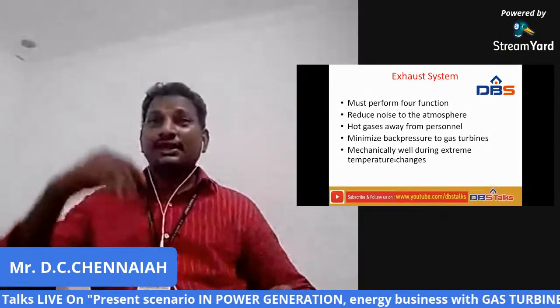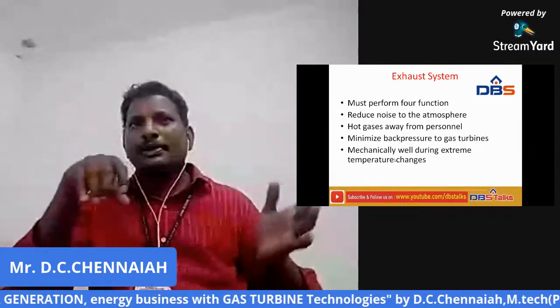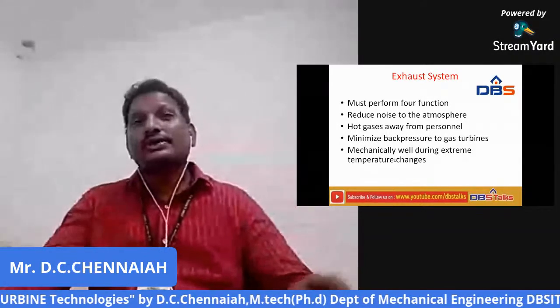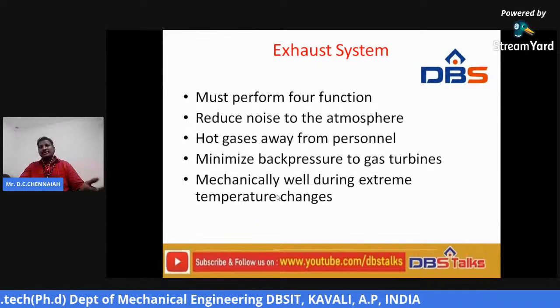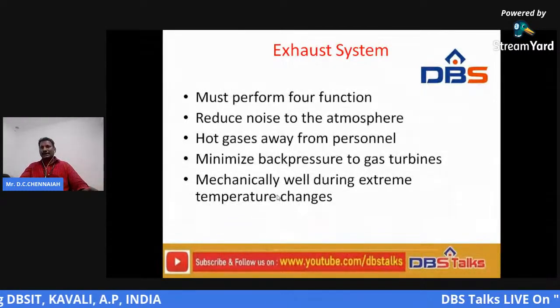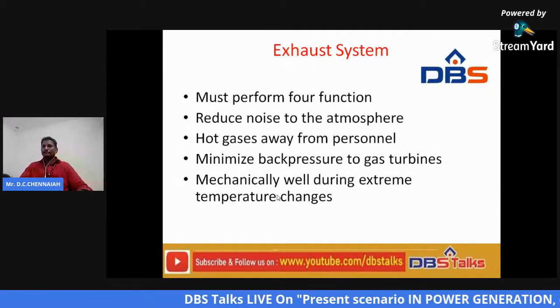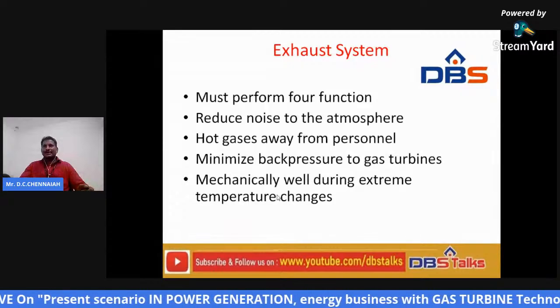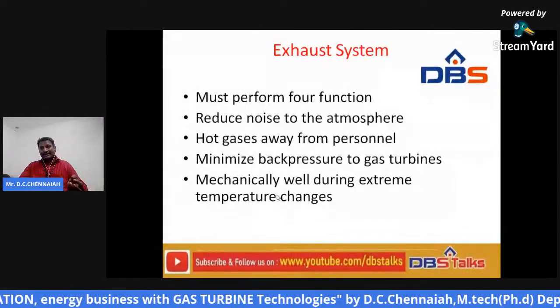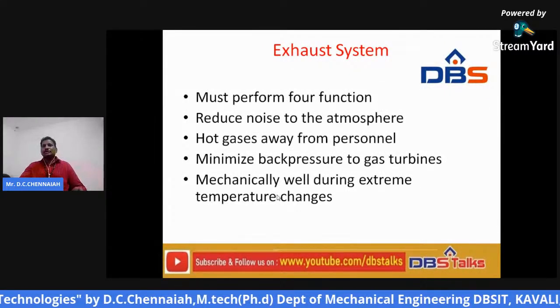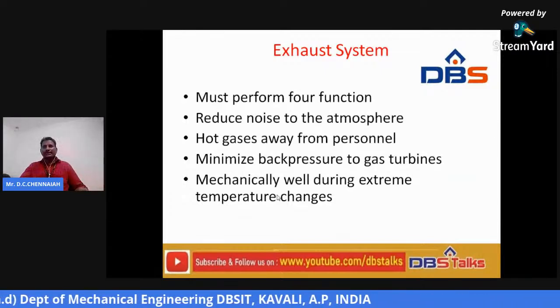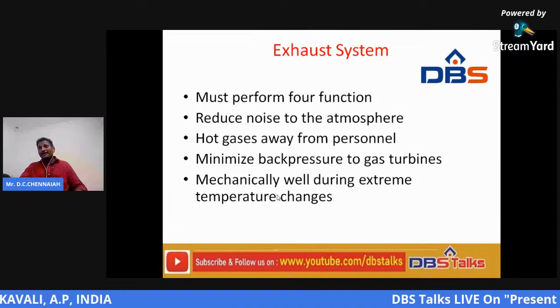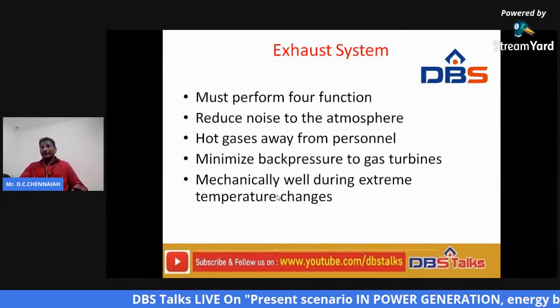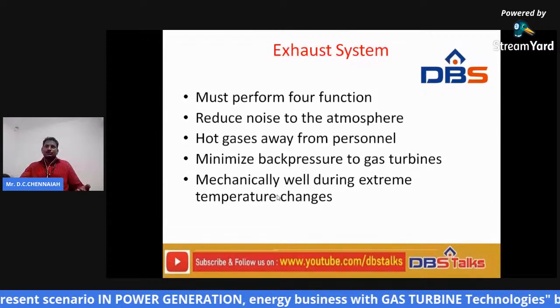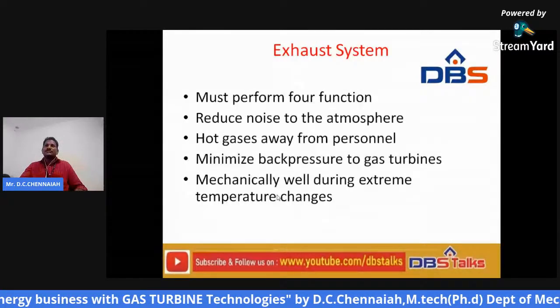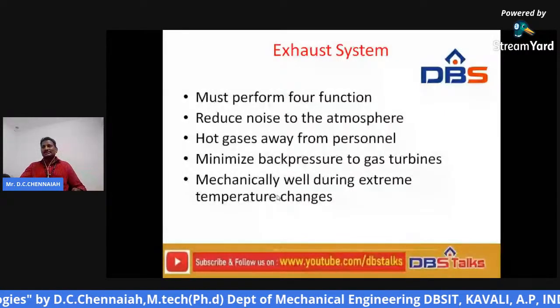So from the highest pressure, if we keep the least back pressure, we allow the gases to expand further in the gas turbine unit. If the gases expand further, the rotational work or turbine work improves. This must be achieved through a proper exhaust system, because it has to receive the exhaust gases at the least possible pressure, and also remain mechanically sound during extreme temperature changes, since under peak load conditions the gas turbine unit may run at high demand, so the exhaust system must be well suited to accommodate such higher temperatures.